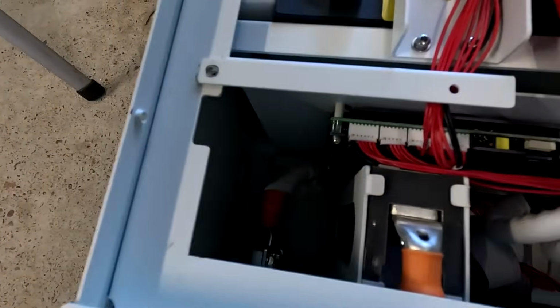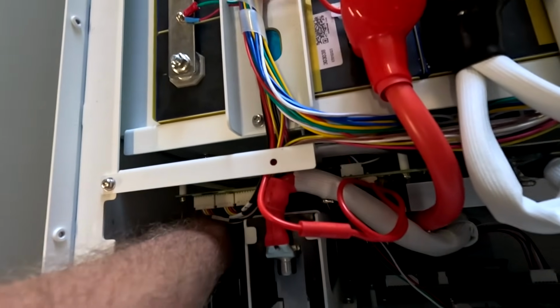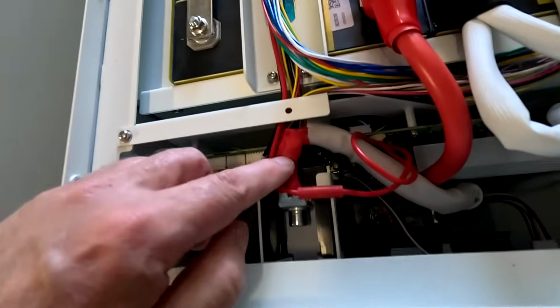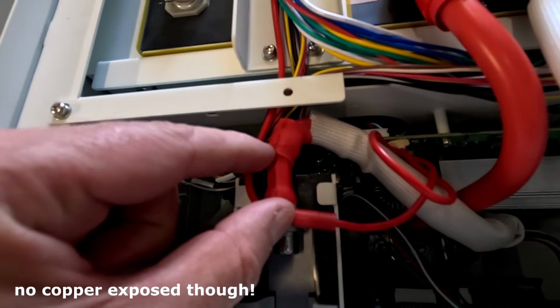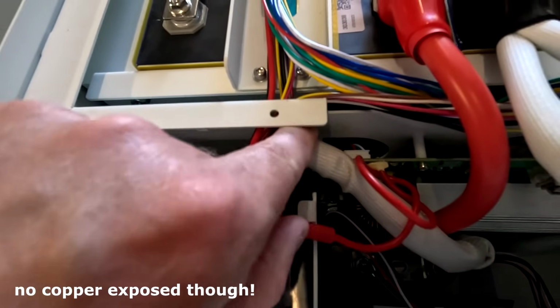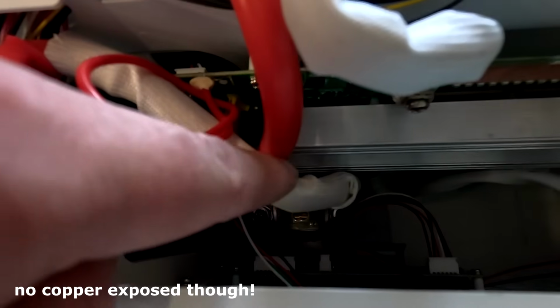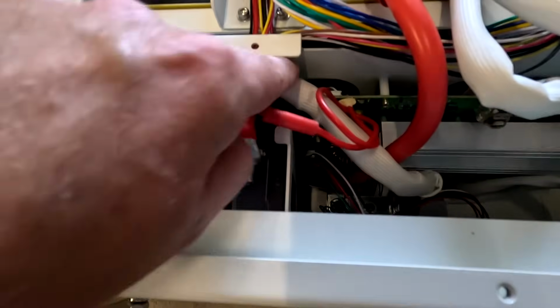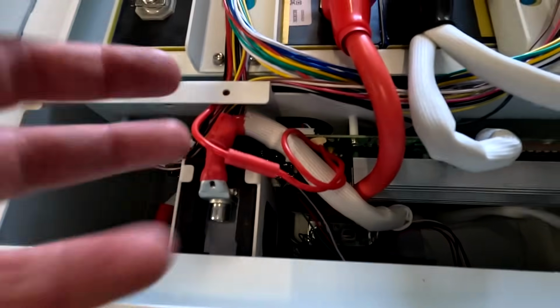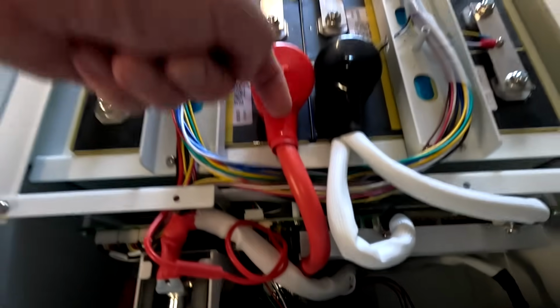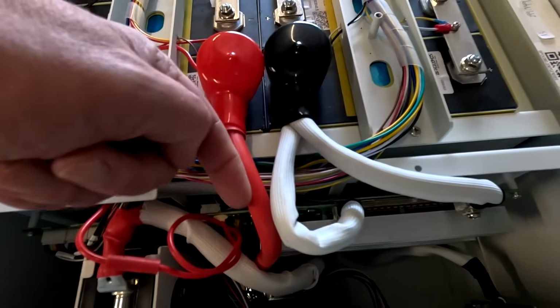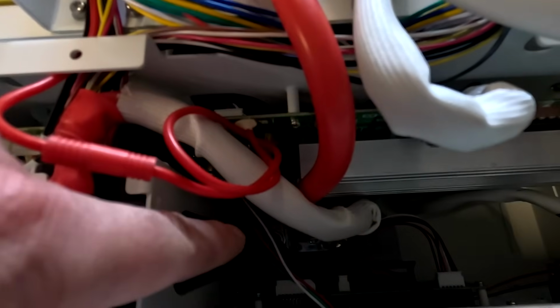This is pretty much the same as in our do-it-yourself box, and yep, it does the same sharp bend, you can see it here as well. It comes from the ring lock and then bends pretty sharp over and goes down to the fuse. So I'm really not a big fan of that. This one is absolutely fine, it comes in a nice slow bend all the way down to the fuse.